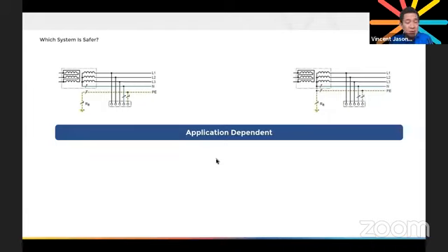That's why even in hospitals, it's in the standards. In the US, it's NFPA 99. In Europe and the rest of the world, it's under IEC 60364-7-710, and locally in the Philippines, under the PEC's Article 5.17.